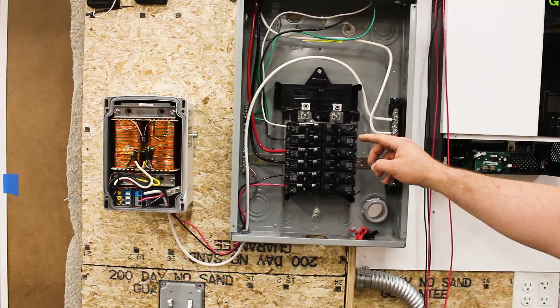Right here, I have a 50 amp, which is gonna go off to the house, and that's where this neutral is gonna go right here. So that 50 amp with 6 gauge wire neutral is gonna go off to the house through the transfer switch, and this 30 amp feeds the auto transformer, which comes back with the neutral. Now yes, this should be in conduit, but I need to test this whole setup before I go and buy all these fittings and conduits and everything else. I need to make sure that it actually works.